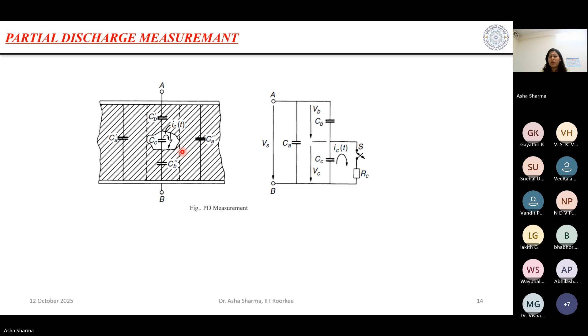In the case of the transformer also, if some partial discharge is happening within my transformer oil, there will be propagation of some waves because of that, and those are detected by the acoustic sensor. If this is the whole body of the transformer, at certain points we use the acoustic sensors. These acoustic sensors sense the propagation of the wave, and that can be detected by my measurement or the CRO. But again, the accuracy we are not certain about.